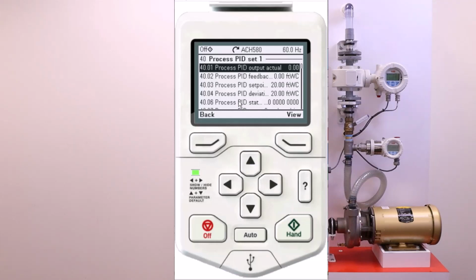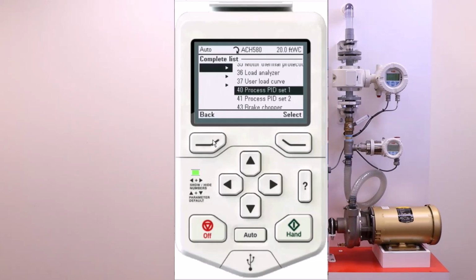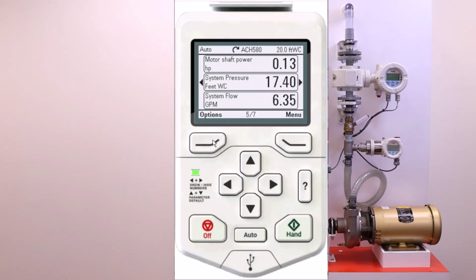So right now, the system is set to do 20 feet of water column in auto mode. If I go back to auto mode now, you see 20 feet of water column is showing up. That's our set point right now. And the drive is coming up to speed to get up to that 20 feet of water column. And I can back up and we can look at our display. Here's our motor shaft power. Here's our system pressure in feet of water column. Here's our gallons per minute. The drive's still ramping up.